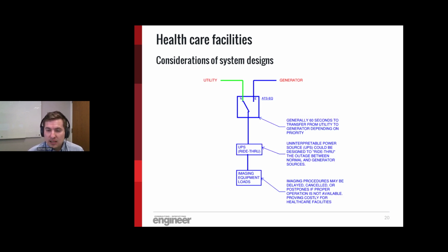Next thing I want to highlight here is what some folks on the call might know, which is ride through. With the utility to generator transfer, there's going to be an outage, if you will, or delay. I'm sure Brian will get into this in his slides later on, but there'll be some loads downstream where you can't even see a blip. You don't even want an outage.